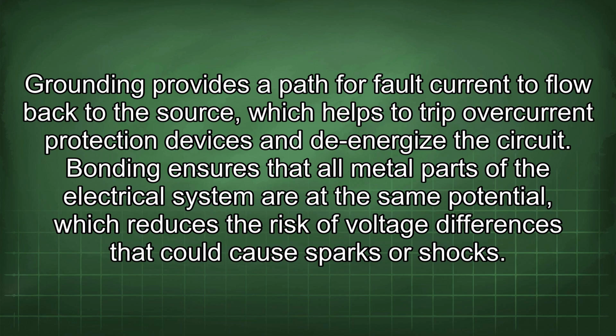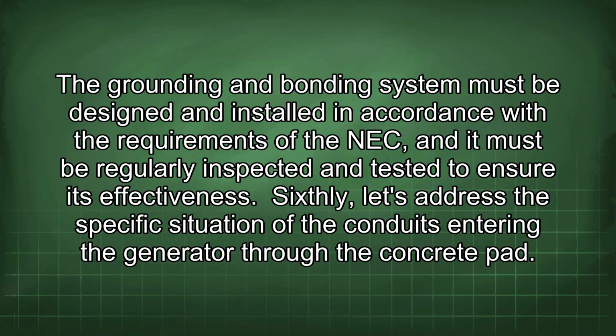Bonding ensures that all metal parts of the electrical system are at the same potential, which reduces the risk of voltage differences that could cause sparks or shocks. The grounding and bonding system must be designed and installed in accordance with the requirements of the NEC, and it must be regularly inspected and tested to ensure its effectiveness.